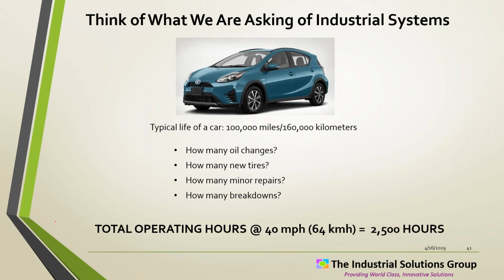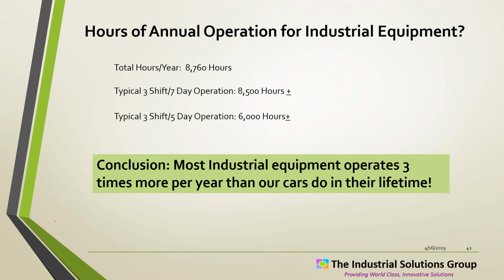So if I drive an average of 40 miles per hour, 60 some kilometers per hour, that 100,000 miles translates to 2,500 hours of operating time for that car. Compared to what we're asking for a pump, we have 8,760 hours in a year. These pumps are doing 6,000 hours, even if they're running 5 days a week. More than 8,000 hours if they're running 7 days a week. So, a typical piece of equipment in our plants runs 3 times as much in each year than my car does in its lifetime with me. This is good equipment. That's why it's so expensive compared to a regular automobile.